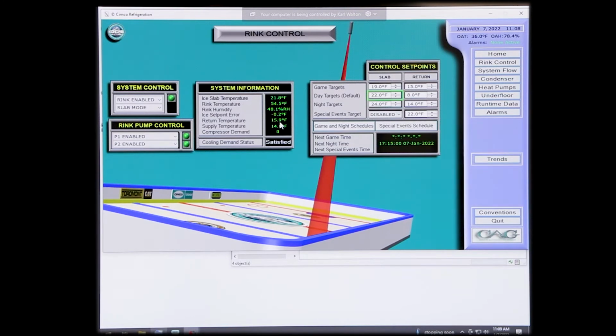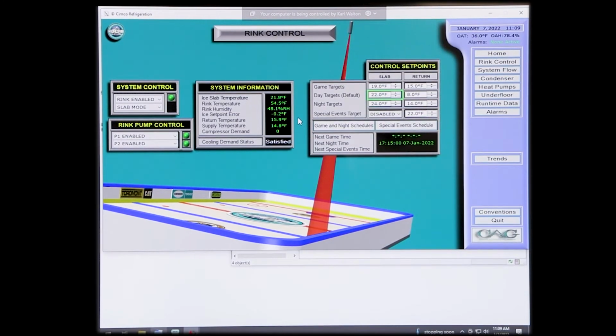If you're running 3 machines and you've reached that max DT of 10, at 12 degrees you'll start to see compressors start to knock off because you've already reached your set point. It's already got the glycol cold enough. We know we've got that 10-degree spread on the return glycol and the slab temperature. Now the rest is basically X time. We're as cold as we need to go. Let's just wait for that cold to get up through the slab. Ice thickness, all that, we won't even get into that. All right.